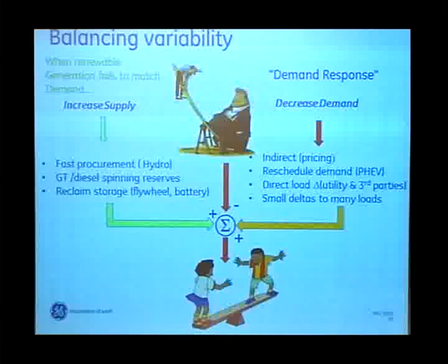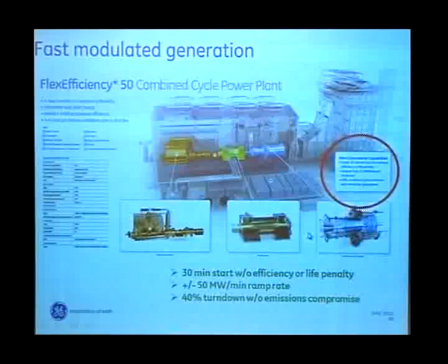And then there are places where we can make small changes to many loads. I'll shamelessly show our newest Flex 50 combined cycle power plant - a big plant. This isn't necessarily what you'd need to modulate, but the takeaway is that this is a big, complex system that can start up quickly - 30 minutes is quick on the scale of starting up equipment. You can ramp it up and down 50 megawatts a minute, and get 40% turn down from rated power while still in compliance with emissions. It's an important class of technology, and I'm sure our competitors produce similar things that fit nicely into dealing with variability in renewables integration.